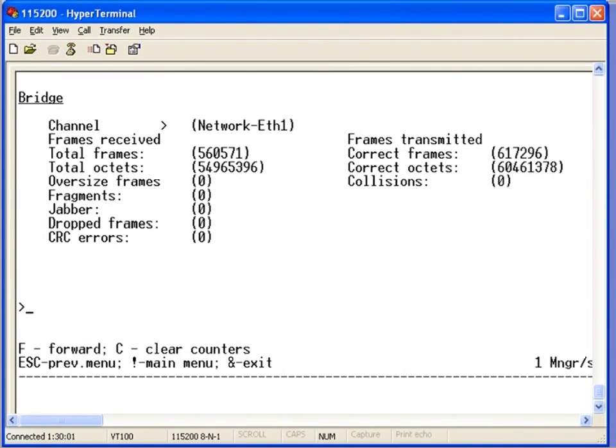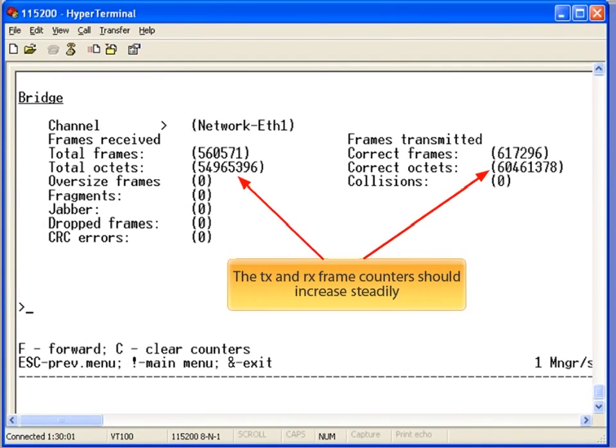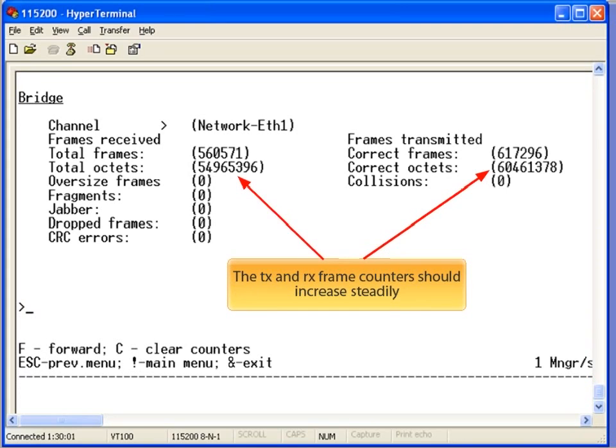You can also monitor the bridge statistics to verify that you have bi-directional connectivity. The transmit and receive frames on the Ethernet port should continually increase. Any CRC errors are an indication of errors at the physical layer.